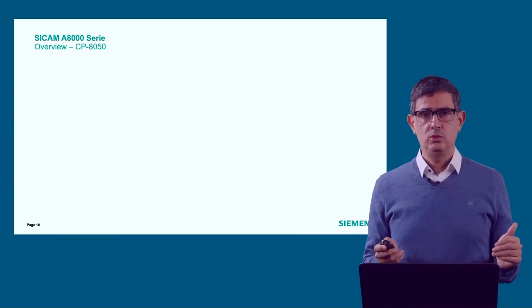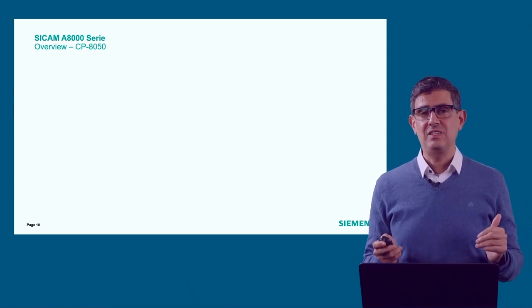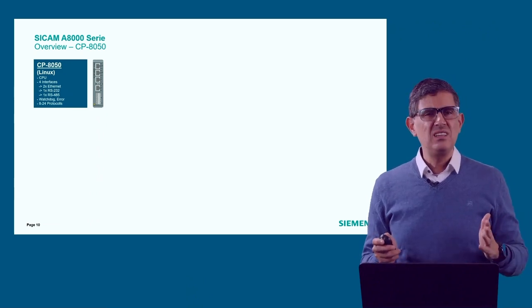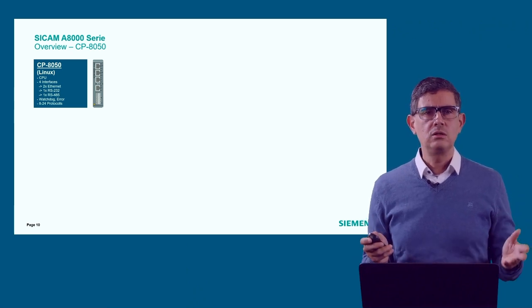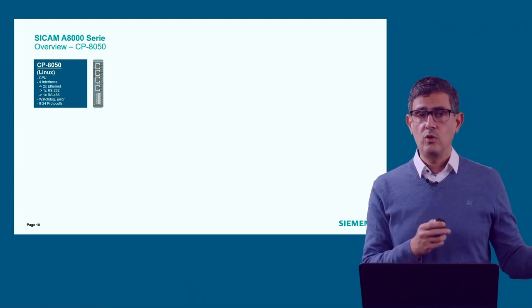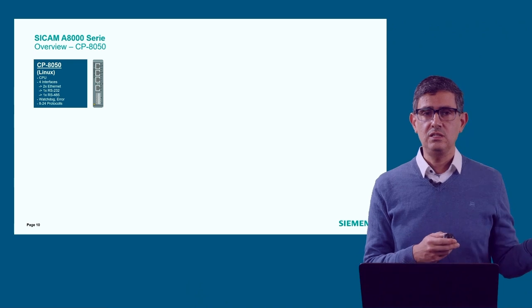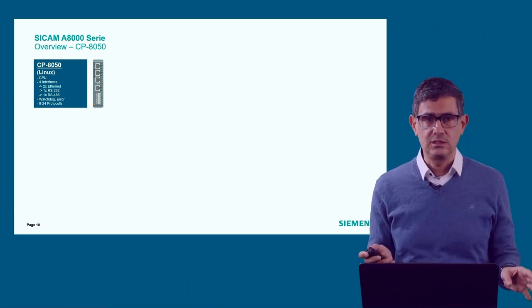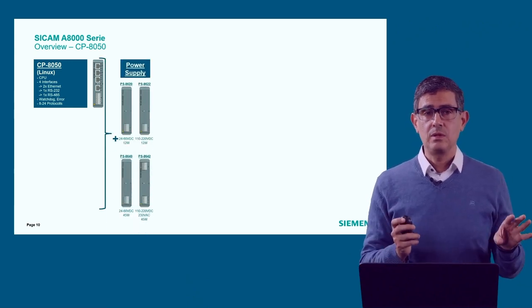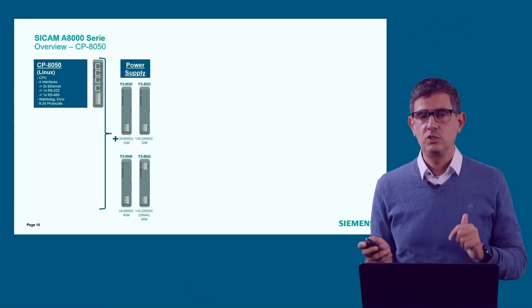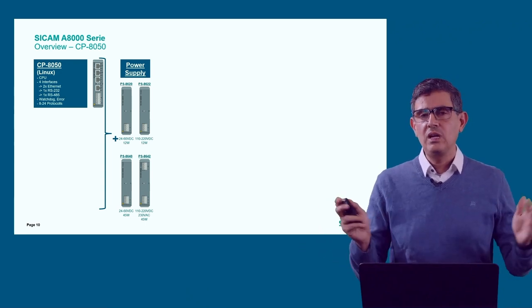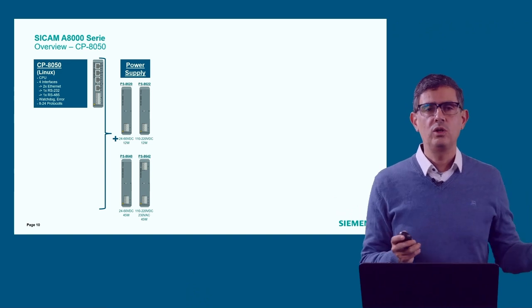After these smaller RTUs we came with the CP8050, which is a very large RTU. Its size is exactly the same as the CP8021, with four interfaces, and the operating system is Linux. As opposed to the smaller RTUs which support only 20,000 data points, here we are talking about 400,000 data points — 20 times the size. You can power up this RTU with the same power supplies used for the smaller RTUs, so you can have the same spare parts for the whole family — one advantage.